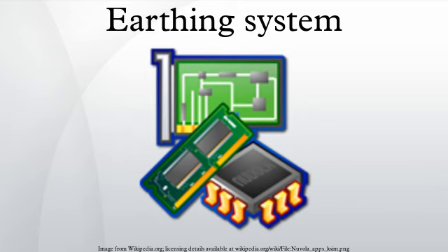If a fault within an electrical device connects a live supply conductor to an exposed conductive surface, anyone touching it while electrically connected to the earth will complete a circuit back to the earthed supply conductor and receive an electric shock. Regulations for earthing systems vary considerably among countries and among different parts of electric systems. Most low-voltage systems connect one supply conductor to the earth.